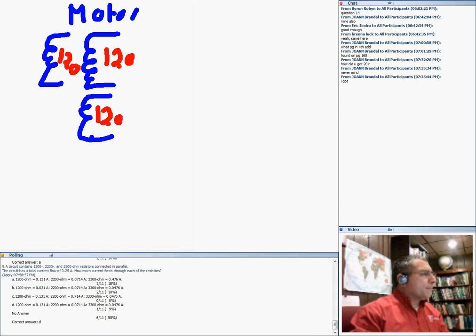If you grab this here, take it all the way to here, and you parallel them - you grab this leg, take it over here - you get yourself a 120 volt motor. Of course this one has to be tied to one leg, the start coil. Let's say it's a 1 horsepower motor.